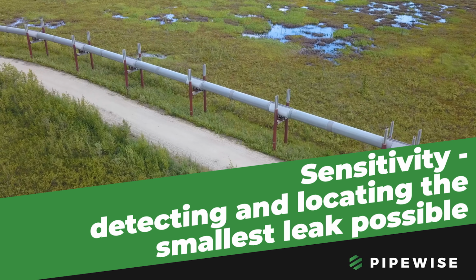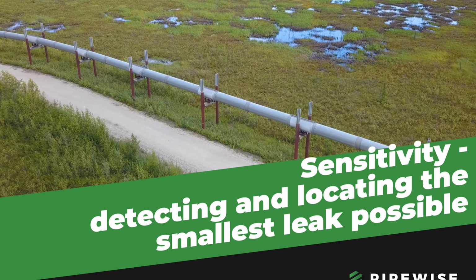Sensitivity, and that's going to be tied to the leak characteristics. So when we talk about leak characteristics, if the system alarms, we're going to be saying you've got this kind of a leak, so you've got this size of leak. If we're saying you've got a 0.6% or a 1% leak, how close to accurate is that? Is it actually a 1% leak or is it actually a 5% leak? Because your response plan and the steps that you would take to deal with that could look very different if you think it's a 1% leak versus a 5% leak.